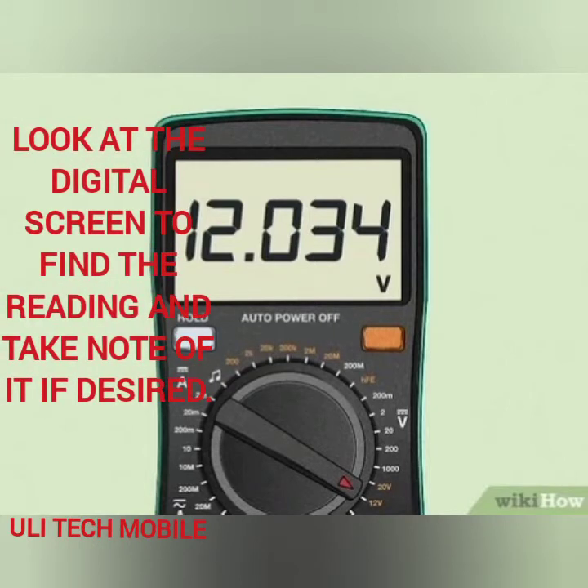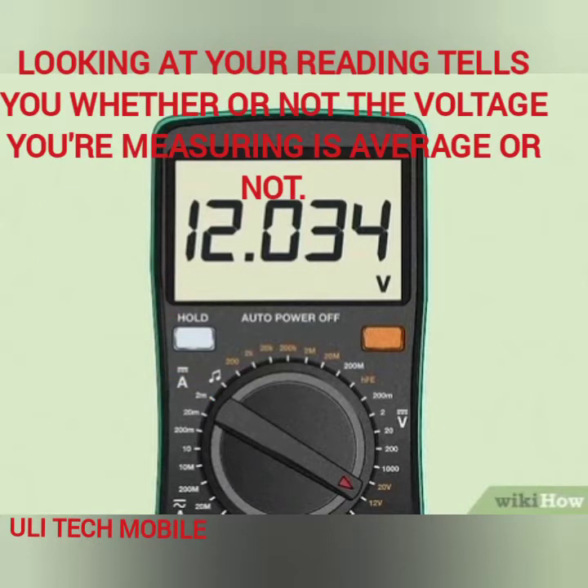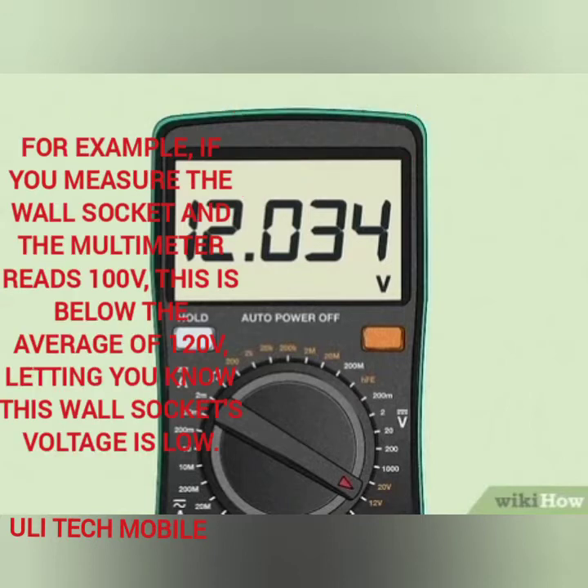Look at the digital screen to find the reading and take note of it if desired. Looking at your reading tells you whether or not the voltage you are measuring is average. For example, if you are measuring the wall socket and the multimeter reads 100 volts, this is below the average of 120 volts, letting you know this wall socket voltage is low.